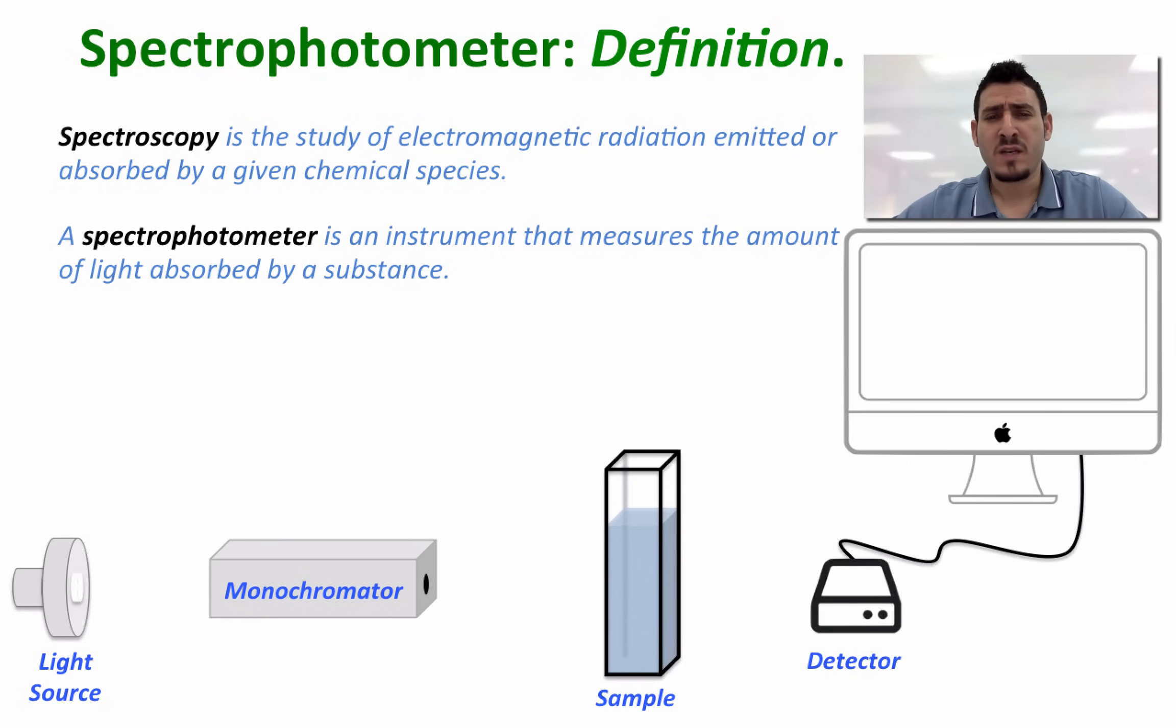The spectrophotometer is made from a light source, a monochromator, a cuvette that's going to contain the sample, and a detector that's connected to a computer that will analyze the data.